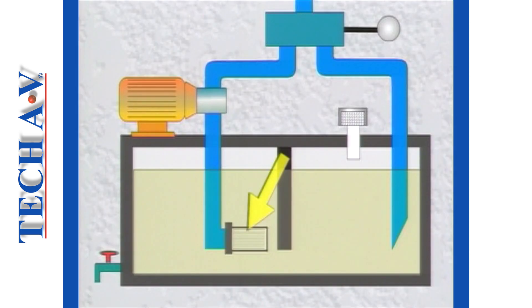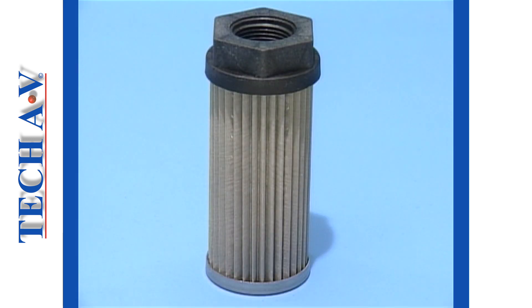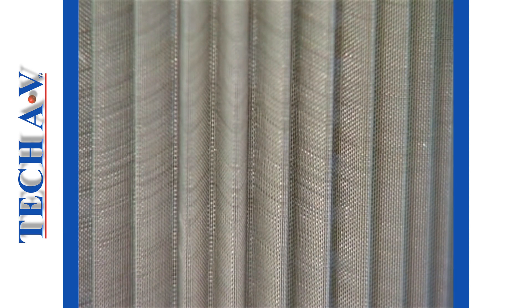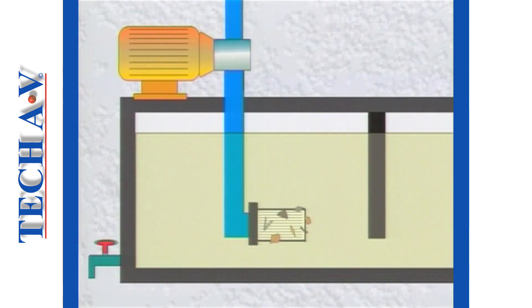Next, we see the suction strainer situated at the suction end of the pump inlet. This is normally constructed from fine wire mesh, having a pore size of around 100 microns. The suction strainer purely offers protection against large particles or objects, such as rust flakes, bits of gasket material, or other debris, from entering the pump and destroying it.